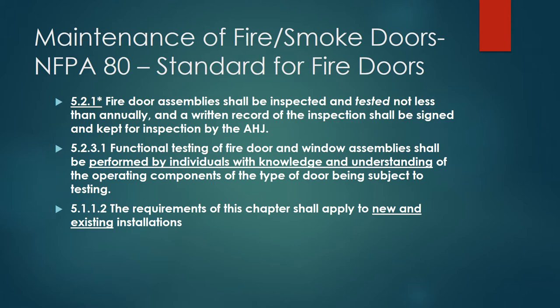Functional testing of the fire door and window assembly shall be performed by individuals with knowledge and understanding of the operating components of the type of door being tested. Think back to that anatomy diagram — how many people in your department or facility have a really good understanding of all those door components? Also, per 5.1.1.2: the requirements of this chapter shall apply to new and existing installations — you do not get grandfathered on this one.